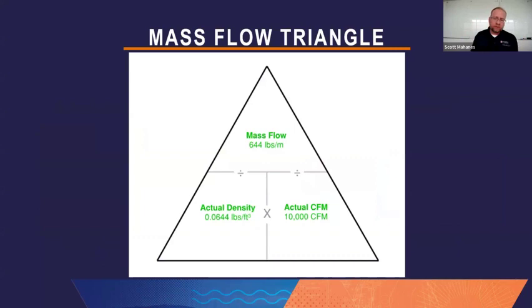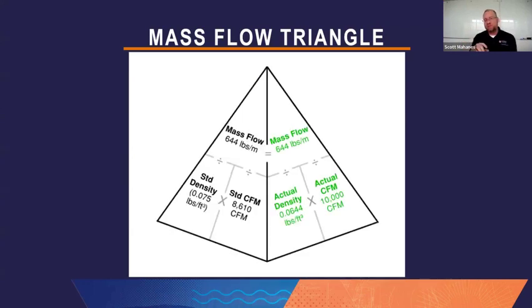The math is simple. You take the actual air density, multiply it by the volume, you get the mass. And I realized when I started thinking through this mass flow situation that there's another side to the triangle, another dimension you could talk about, which would be a different density side. Now, we said that mass doesn't care about density. It's the same value no matter what. So if mass is 644 pounds on the actual density side, I can move it to a standard density side of the triangle at 644 pounds. Divide that then by standard density, and you get a standard CFM value of 8610. Now, that's very different from 10,000 CFM, but what's really going on here?